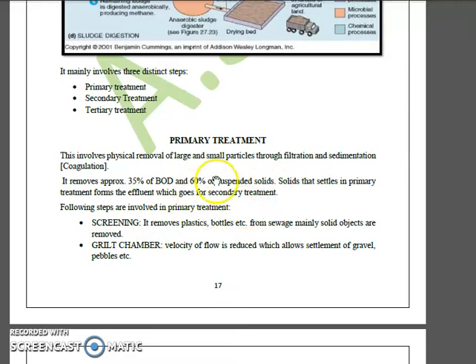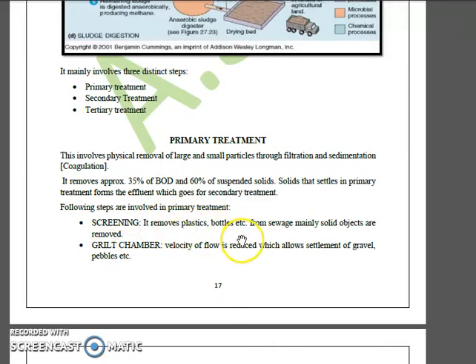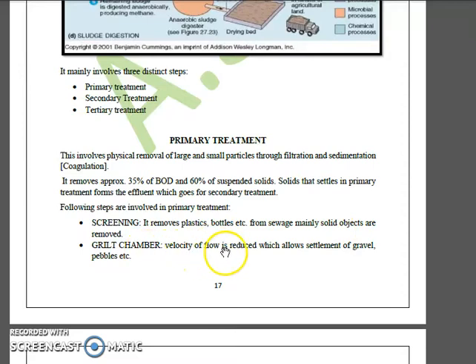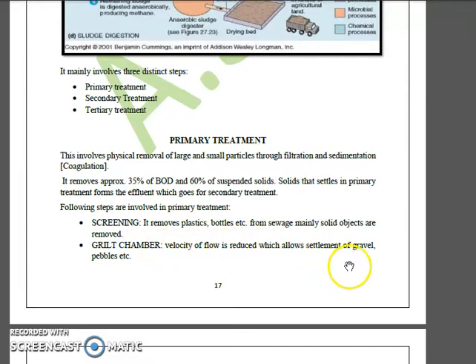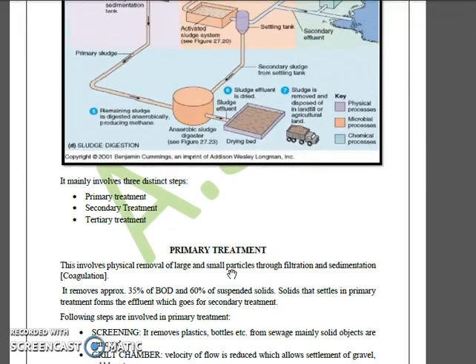As shown in the picture, the first step is screening, which removes bottles, plastic, cloth, and solid objects from sewage. Then there is a grit chamber where the velocity of the flow is reduced, allowing settlement of gravels, pebbles, and grit.